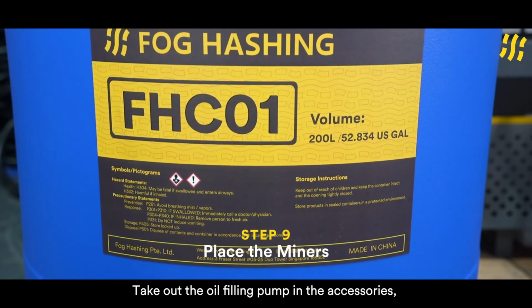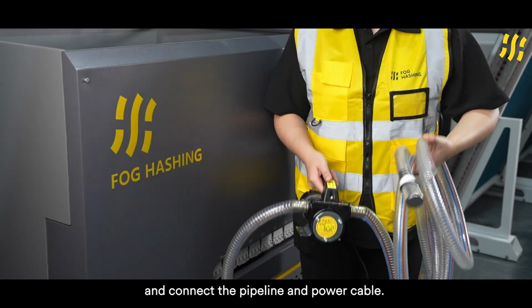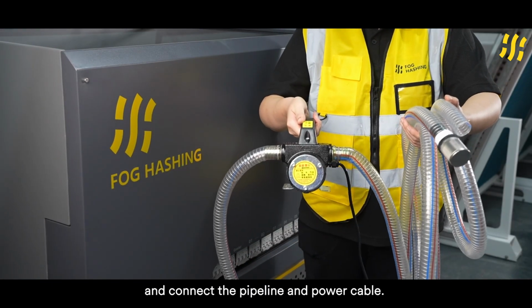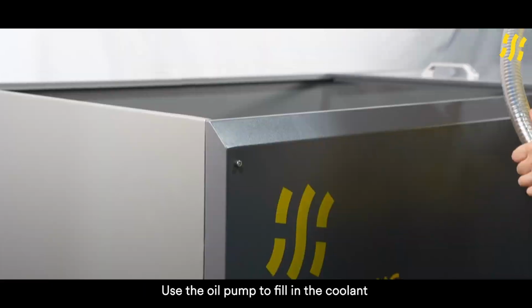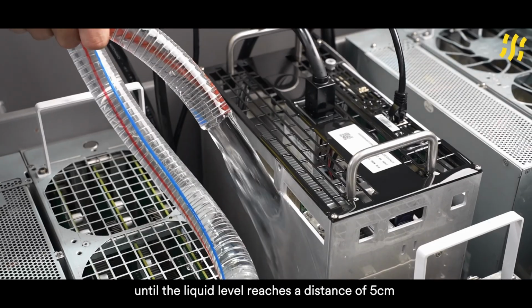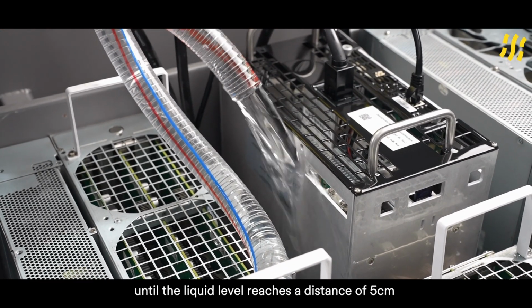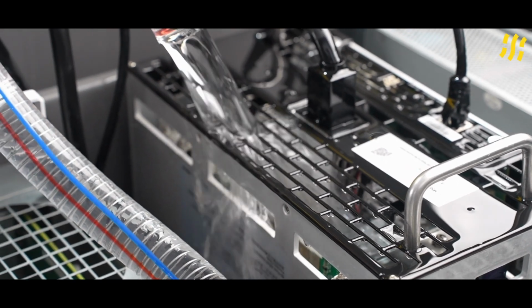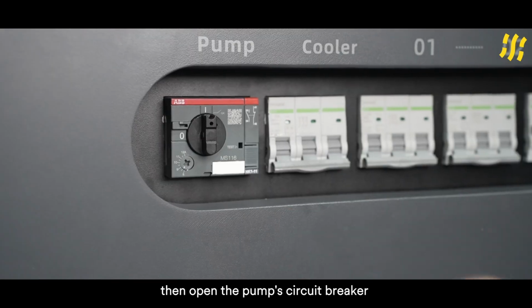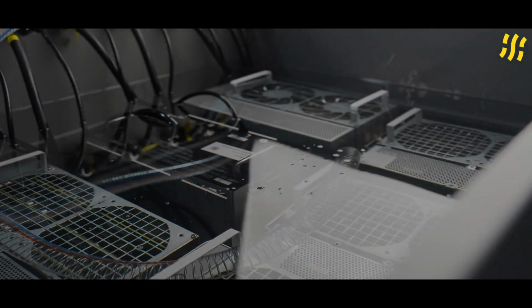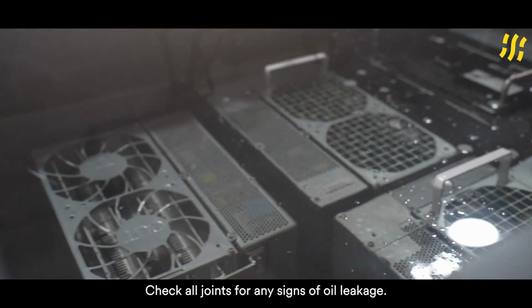Take out the oil filling pump in the accessories, and connect the pipeline and power cable. Use the oil pump to fill in the coolant until the liquid level reaches a distance of 5 cm from the overflow plate. Cover the top of the tank. Then open the pump circuit breaker and run a test for 30 minutes. Check all joints for any signs of oil leakage.